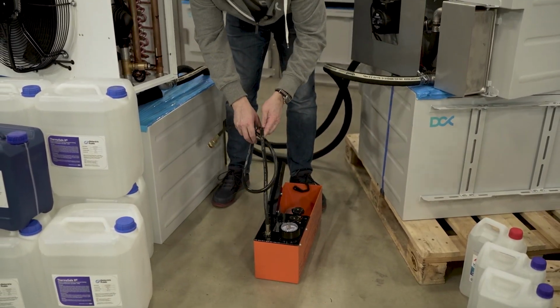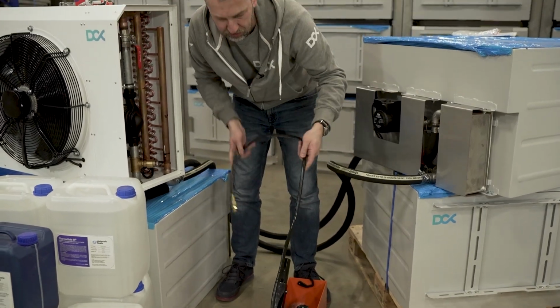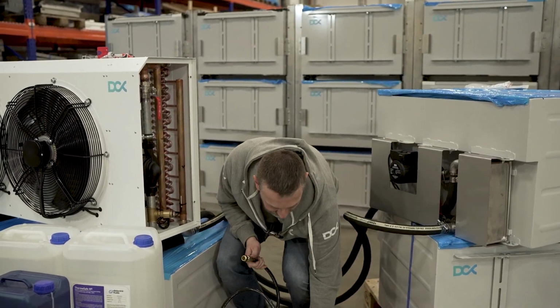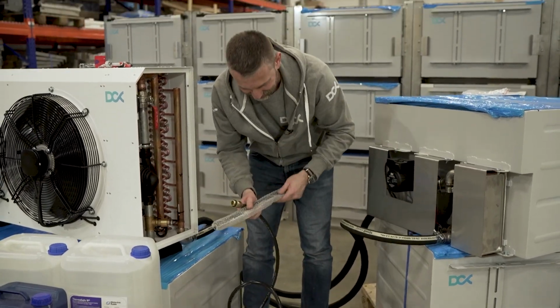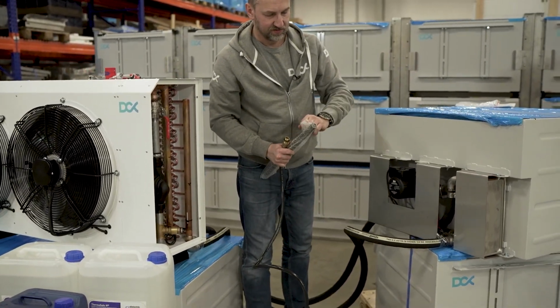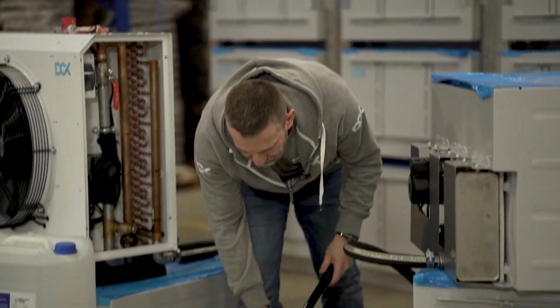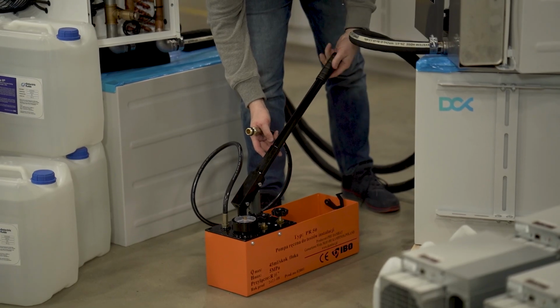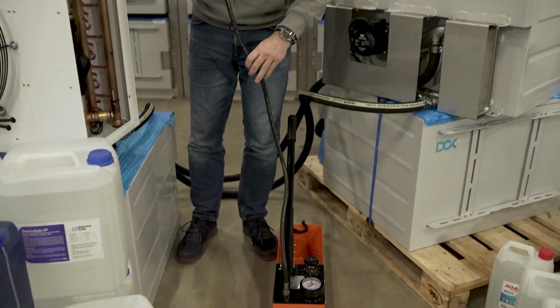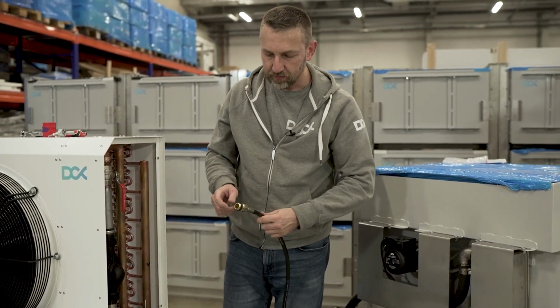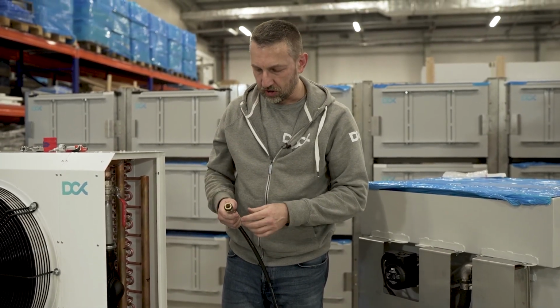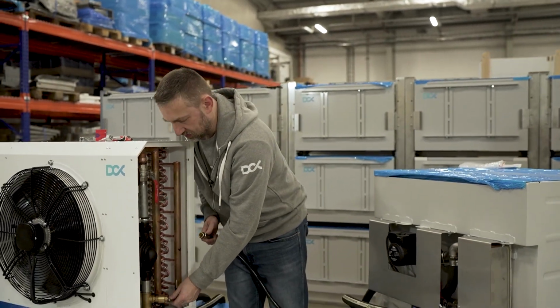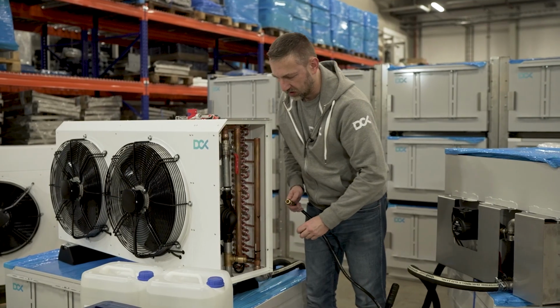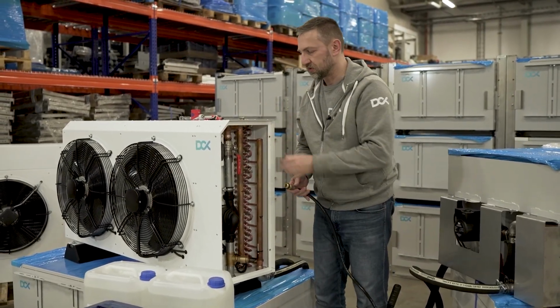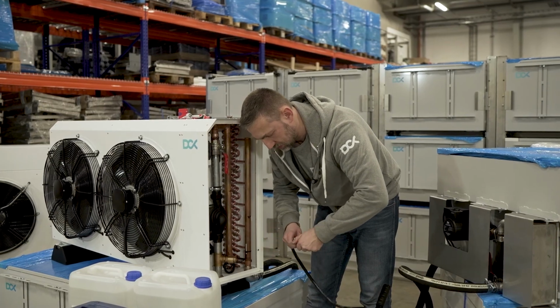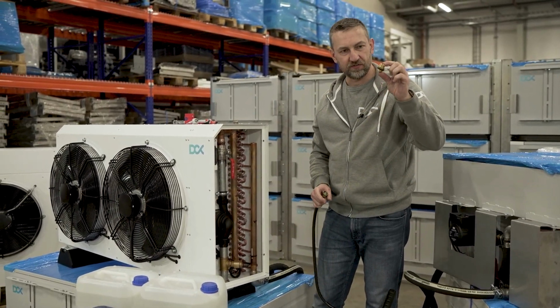So it's a simple component, easy to operate, but there are a few small items which we need to remember. You will see the handle here. So that's just the handle of that pump. Just attach it here. To fill the system, we need to connect the pressure pump hose to the one-way valve on the ICP40. So take that silver cap off. We can take that fitting here.